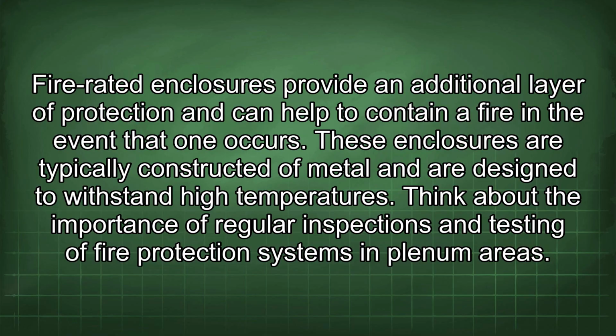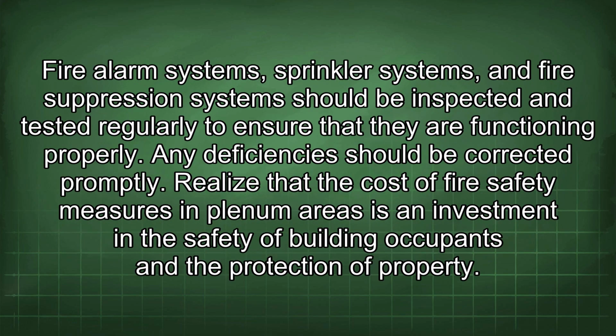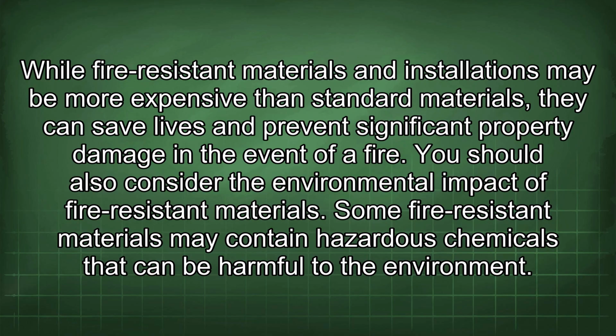Think about the importance of regular inspections and testing of fire protection systems in plenum areas. Fire alarm systems, sprinkler systems, and fire suppression systems should be inspected and tested regularly to ensure that they are functioning properly. Any deficiencies should be corrected promptly. Realize that the cost of fire safety measures in plenum areas is an investment in the safety of building occupants and the protection of property. While fire-resistant materials and installations may be more expensive than standard materials, they can save lives and prevent significant property damage in the event of a fire.